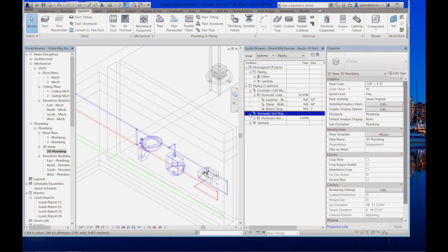Let's talk about that. The system that has 32 gallons per minute actually has to have a lot more water flowing through it. Okay, if we want to maintain the same sort of pressure, not have it be incredibly high pressure, what we need is actually a bigger pipe. And that's what we're going to get to, is that you can use all this to help you size the pipes. So let me show you to connect the sanitary in, and then we'll demonstrate how that works.